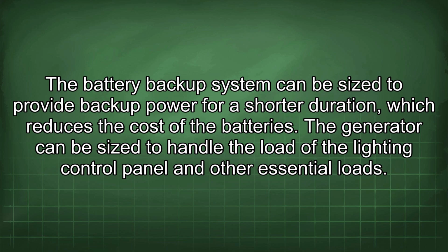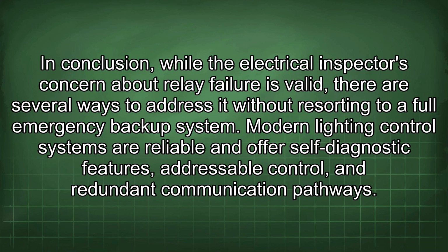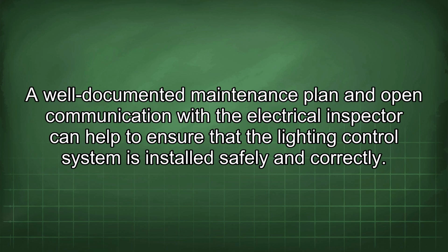The battery backup system can be sized to provide backup power for a shorter duration, which reduces the cost of the batteries. The generator can be sized to handle the load of the lighting control panel and other essential loads. In conclusion, while the electrical inspector's concern about relay failure is valid, there are several ways to address it without resorting to a full emergency backup system. Modern lighting control systems are reliable and offer self-diagnostic features, addressable control, and redundant communication pathways. A well-documented maintenance plan and open communication with the electrical inspector can help to ensure that the lighting control system is installed safely and correctly.